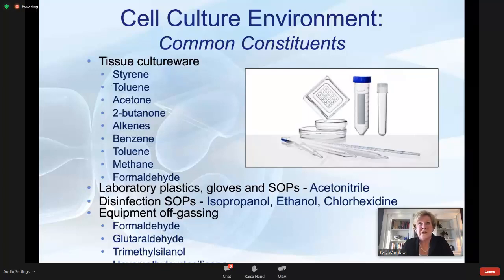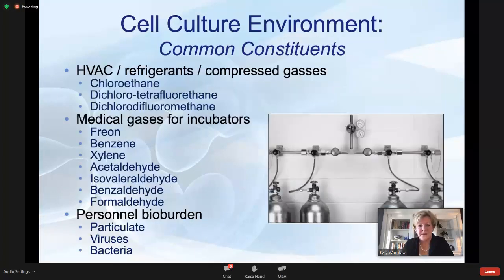We would typically try to order our equipment as early as we could, plug it in, and let it run outside the laboratory so that it was off-gassing outside of our laboratory space. We were even cognizant of when we replaced gasketing. We tried to take care of our equipment ourselves, and we tried replacing gasketing in the incubators. We'd actually try to off-gas that gasket before we brought it into the laboratory. Equipment, gasketing, repairs can allow the off-gassing of cytotoxic VOCs for months, if not years. Your own refrigerators, your freezers, as they cycle to maintain the temperature, can release VOCs. The medical gases supporting the incubators have a large number of VOCs, so inline filtration is key.